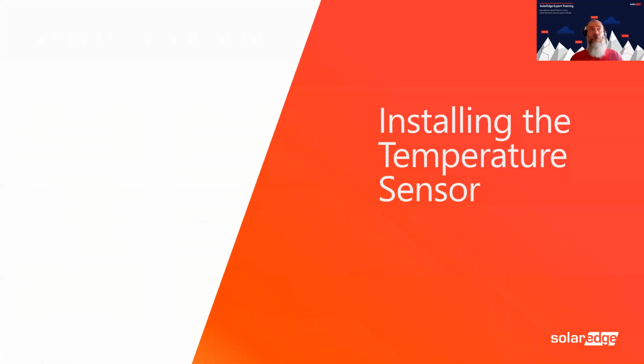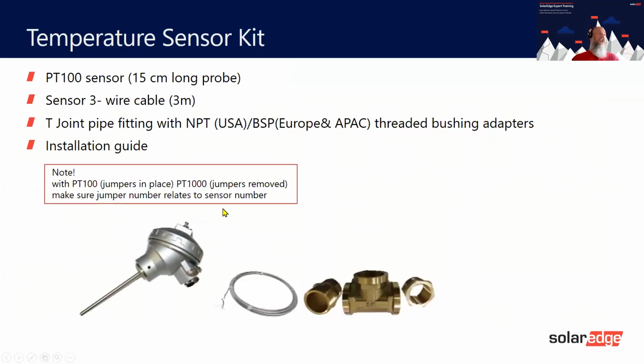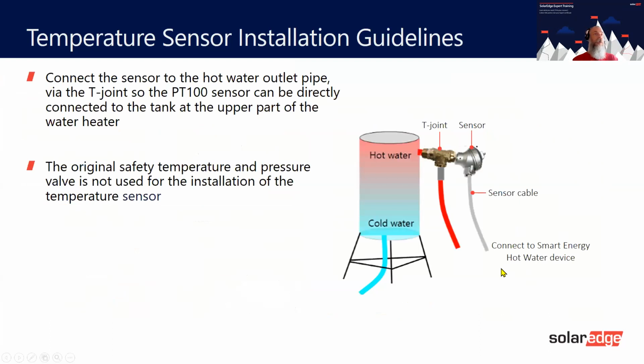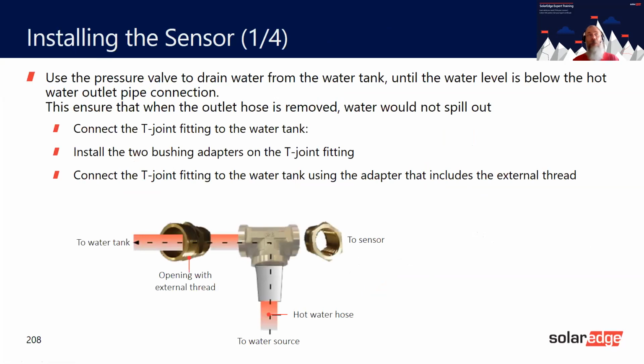And then the last thing I want to show you is the temperature sensor. Basically, we have a temperature sensor in here, PT100. Any PT100 sensor you'll be able to use. You simply configure it into the inverter. Once it's configured into the inverter, you'll be able to then register your hot water as such. It's only for information purposes at the moment. It doesn't force it to come on for a Legionnaires cycle or something yet, but it will do. We are getting very close to that.